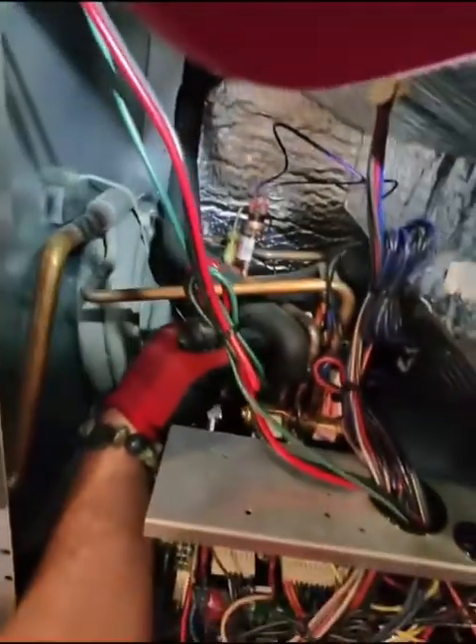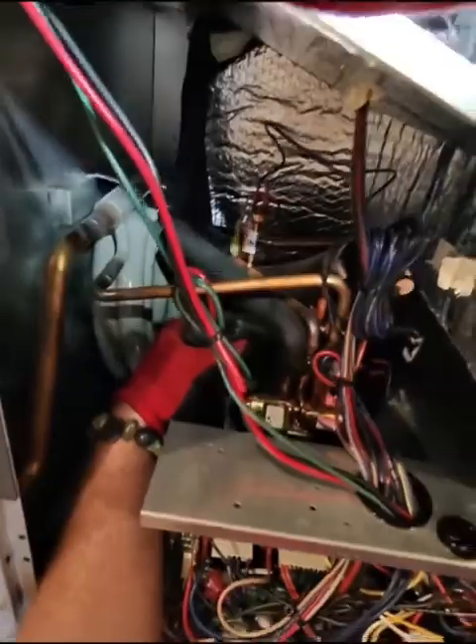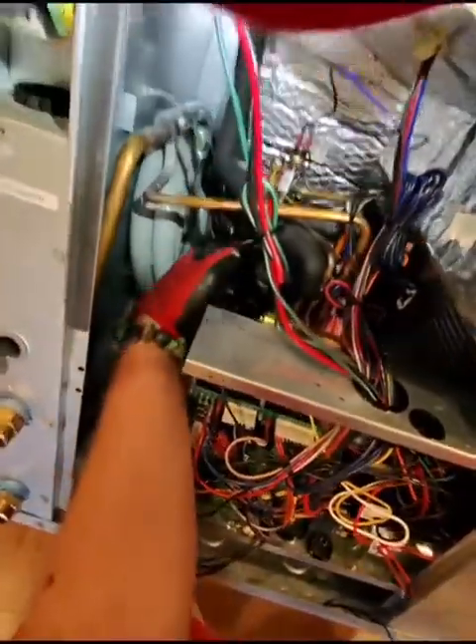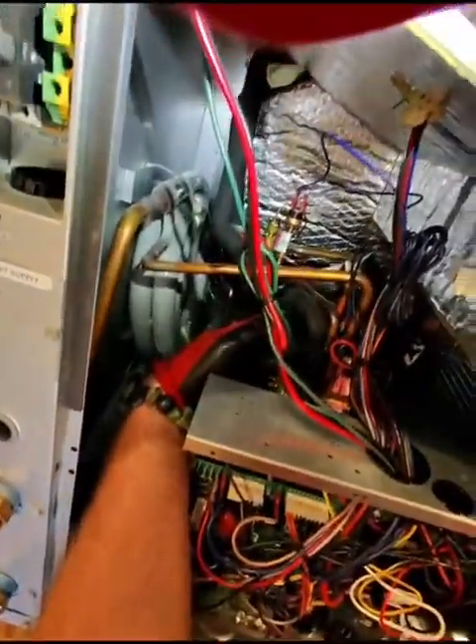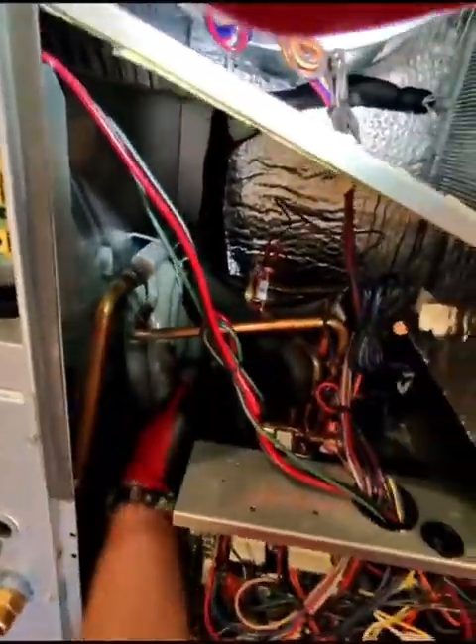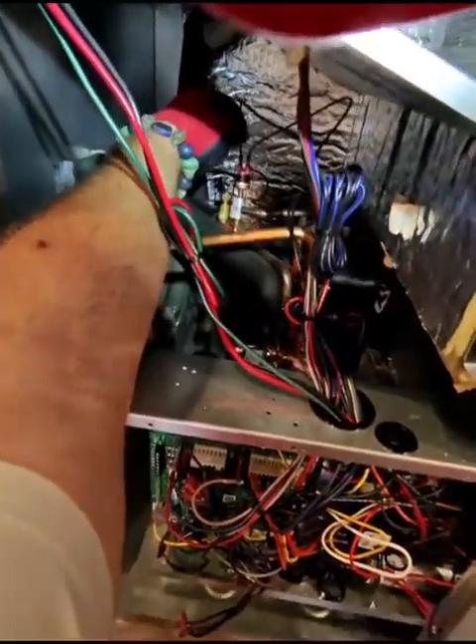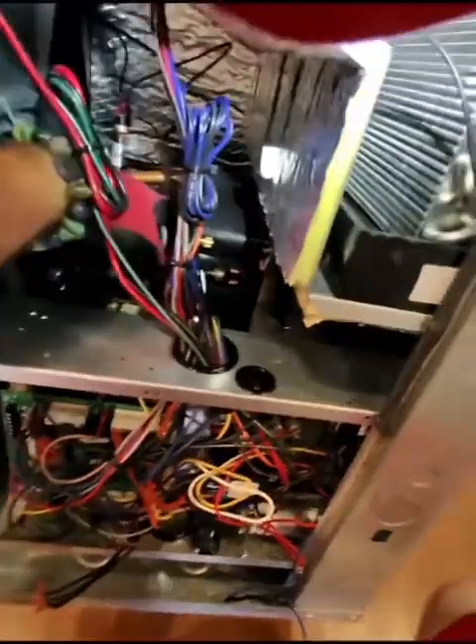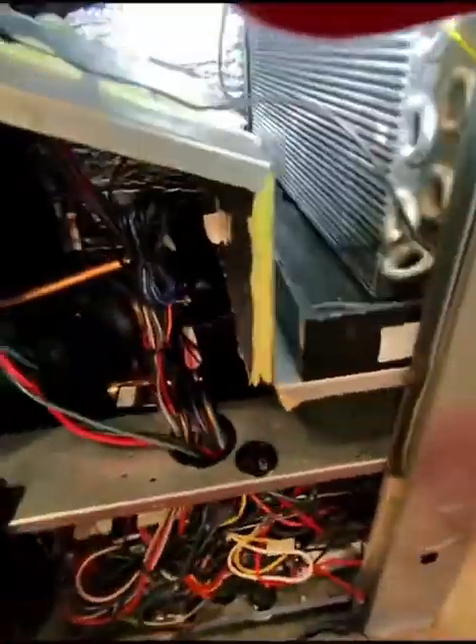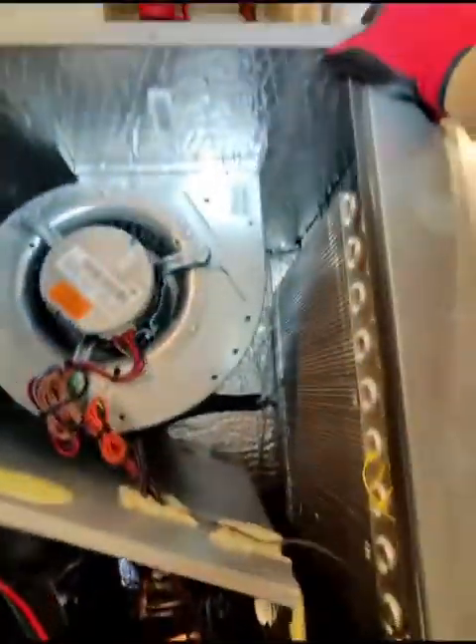Reversing valve. So it can go one way to cool the room, or it can switch the valve and heat the room as well, just by reversing the refrigeration process with this valve right here. This is a pressure switch. This is where you would hook up, which is really not very accessible. You can see, yeah, the hookups are tiny. So this is your heat exchanger. We're going to pull this one out, fix it, and we're going to put a new one in.